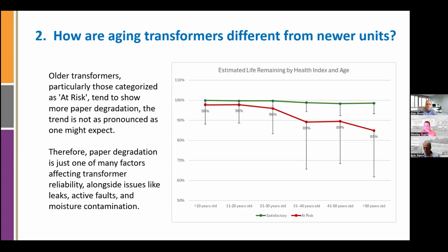And then I'll just explain this chart one last time before moving on. It shows that as the transformer gets older, those that are in the at-risk category, the paper health, as presented by the estimated life remaining, decreases considerably, 15% or more. But it is all other factors that also combine to make that transformer in an at-risk category. Like I said, the active faults, leaks, bushing conditions, gasketing conditions that you need to monitor and maintain.